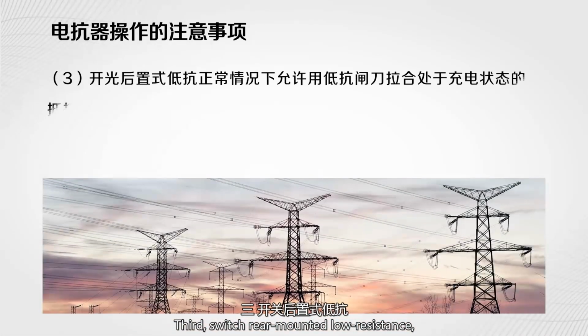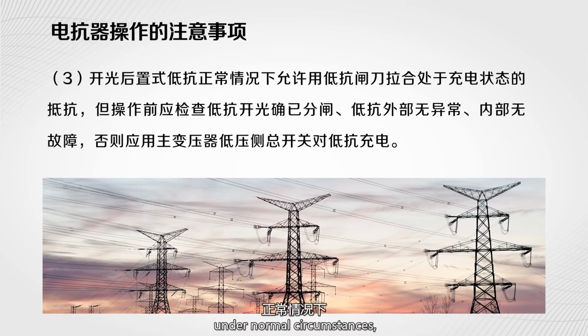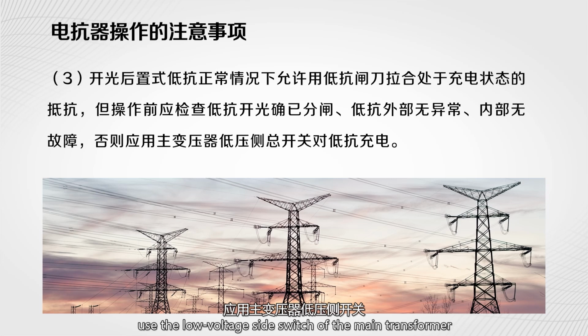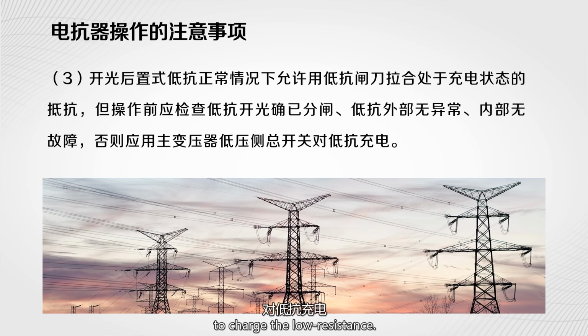Third, switch the rear-mounted low resistance under normal circumstances. It is allowed to use a low resistance knife to pull the low resistance in the charged state, but before operation, it should be checked that the low resistance switch has been opened and the low resistance has no external abnormalities and no internal faults. Otherwise, use the low voltage side switch of the main transformer to charge the low resistance.